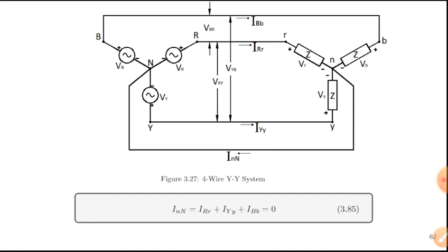In household systems we use a 4-wire system because we cannot directly balance the house load — we don't have exactly three-phase loads, we have individual phases connected to the three-phase source. In the Philippine Electrical Code, there is a standard set by IIEE that the percent balance should be plus or minus 5% unbalanced. If you exceed that, it's a violation. So we design household systems as balanced as possible, using the 4-wire system for safety with a return path from load to source.